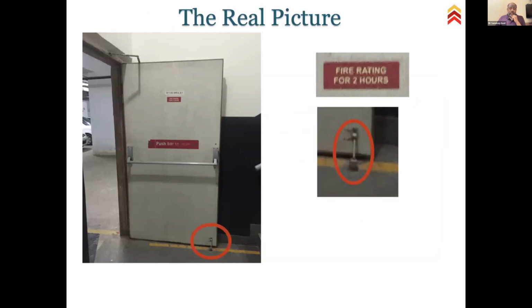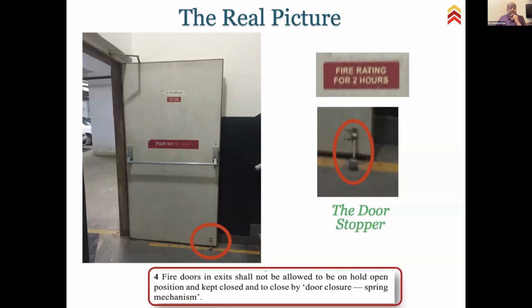Where is the problem? Somebody has mistakenly, unknowingly, because he did not know the why, put a fire door stopper. He knows the what, but not the why. So he knows the code says you have to provide a fire door, a panic bar, a door closure. But the code did not say, Mr. Designer, Mr. Builder, please do not put a fire door stopper. I saw this picture in one of the buildings in Gurgaon, and in the National Building Code of India I proposed to the committee to write a prohibition on providing a door stopper. My committee agreed, and we wrote in the code: not on hold open.